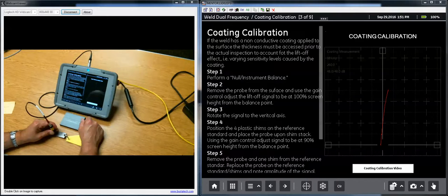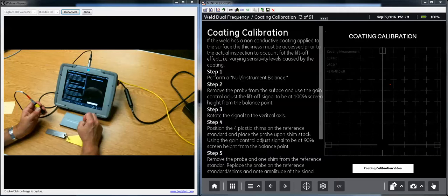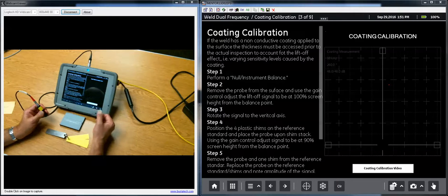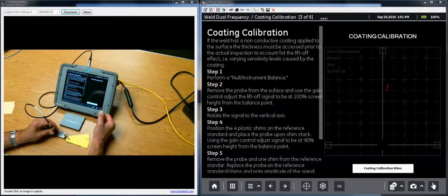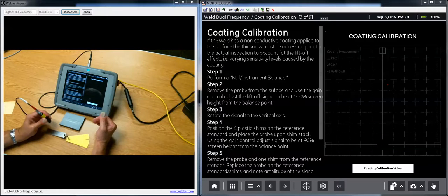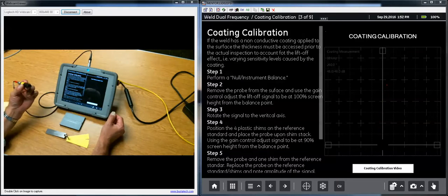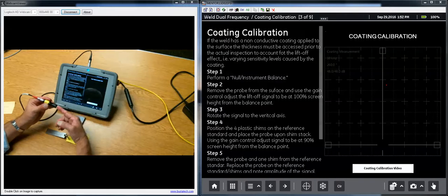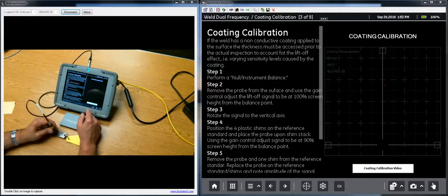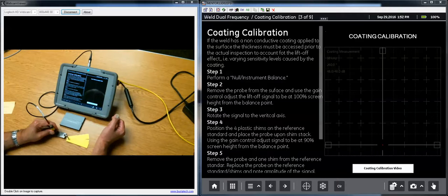And we play a little trick. We'll get into more detail on how the front end of the Mentor instrument works, the Wheatstone bridge, and the cycle table, in a more advanced discussion. But one of the tricks that we can do in the Mentor is configure the Wheatstone bridge at the front of the instrument in different ways on different time cycles in multiplexed operation. We're actually taking advantage of that in this app. We keep most of that in the background where you don't have to think about it too much. But on this panel, and anytime you see the red trace, we've set the instrument up to treat this probe like an absolute probe. So even though it's a differential probe, there are two coils in there. On the shot that we're viewing on the screen, we are only driving one of the coils as an absolute probe. It's a little trick that we can play in the Mentor that's not very readily done on other instruments.